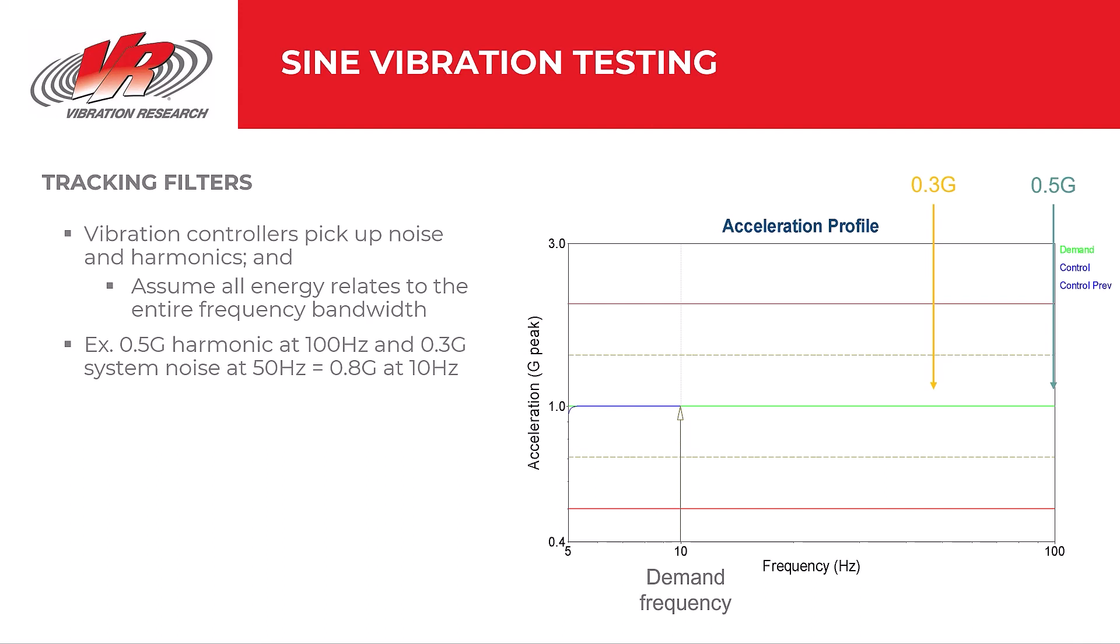If we return to our previous example, let's say there is a harmonic at 100 Hz contributing 0.5 G and system noise at 50 Hz contributing 0.3. When the controller sweeps through say 10 Hz, it'll conclude that there is an acceleration of 0.8 G. The controller adjusts the drive to account for that reading and outputs the remaining acceleration at 10 Hz. The controller now measures 1 G at 10 Hz. However, the device under test is not shaking at 1 G. The drive acceleration has changed and the test is not running at the desired levels.